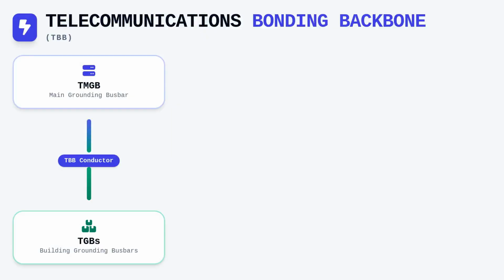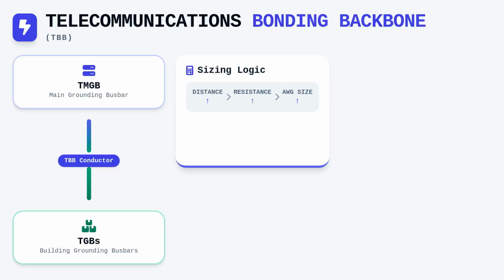The Telecommunications Bonding Backbone, or TBB, is the heavy-duty copper conductor that bridges the gap between the TMGB and all TGBs throughout the building. You calculate the size of this backbone conductor based on the linear distance it travels from the TMGB, which dictates the cross-sectional area needed to maintain voltage stability. Generally, for longer distances, the American wire gauge, or AWG, size must increase to compensate for the higher resistance of the copper path. For example, in many standard building configurations, typical TBB sizing requirements range from 6 AWG up to 3/0 or even 4/0 AWG for extensive spans in high-rise facilities.